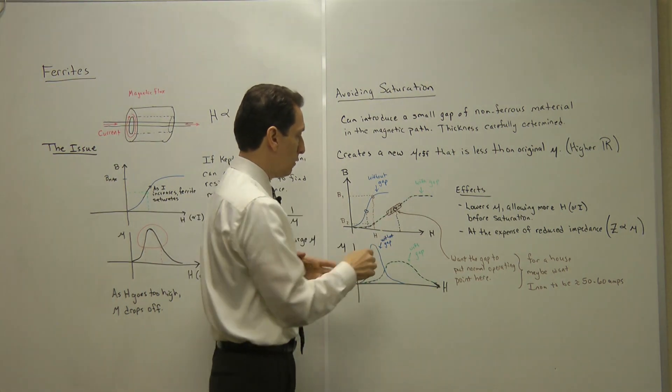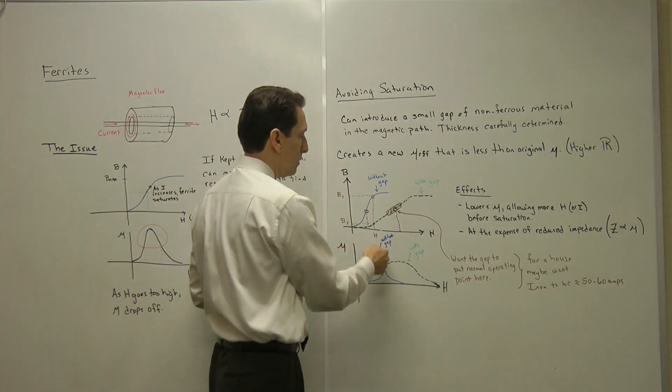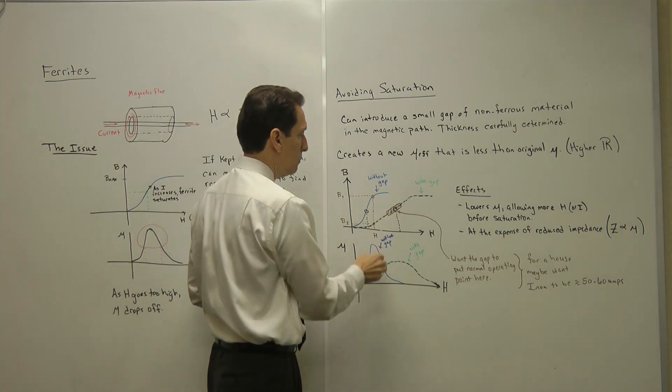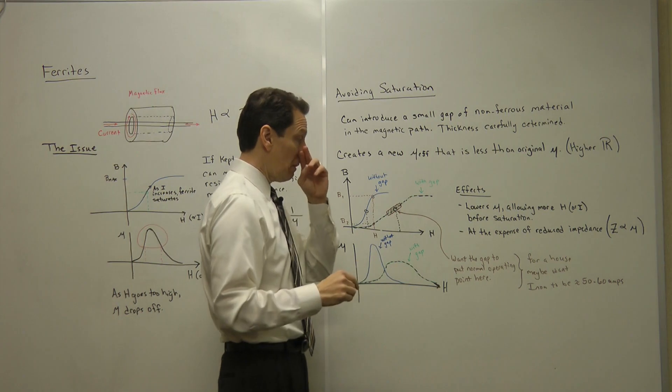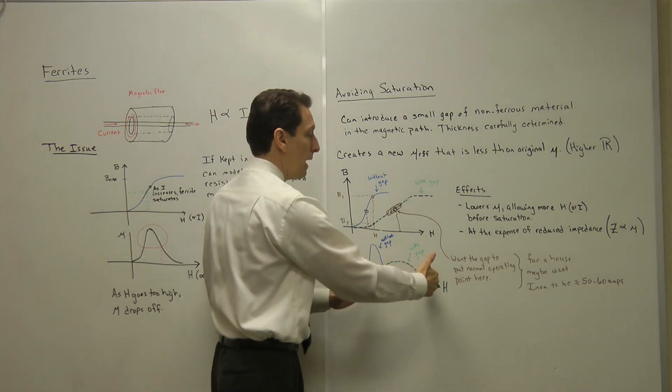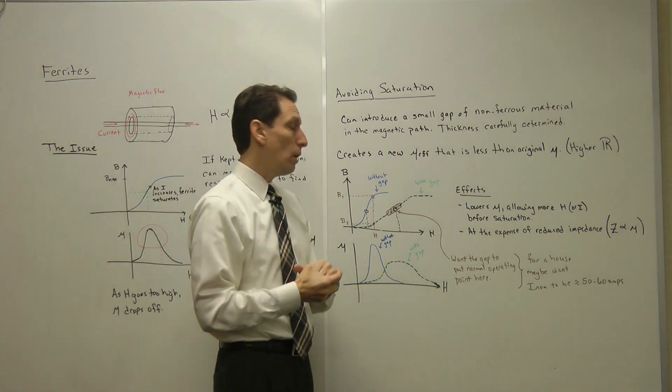What that does to the permeability curve is the original permeability curve looked like the blue one here. It's narrow, it's high peaked. By introducing the gap, it moves the permeability curve out quite a bit further in current, and it also spreads it out, which gives you a nice operating region in which to run.